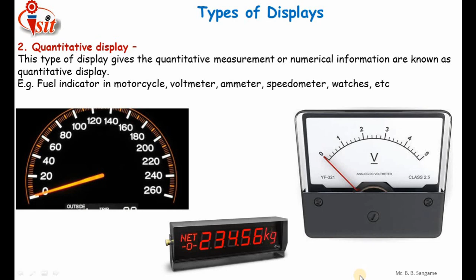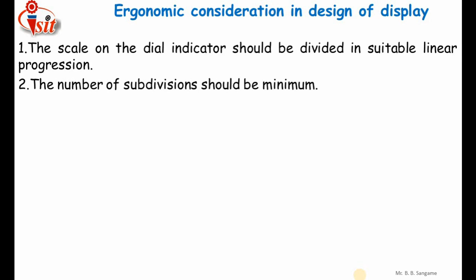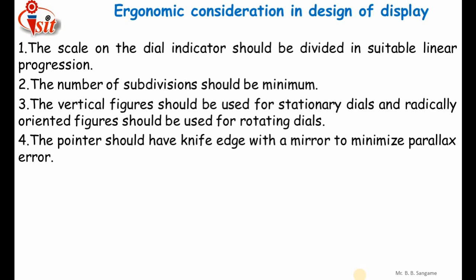Now, the requirements for the scale. The scale on the dial indicator should be divided in a suitable linear progression. The number of subdivisions should be minimum. Vertical figures should be used for stationary dials and radially oriented figures should be used for rotating dials. The pointer should have a knife edge with a mirror to minimize parallax error. Some errors occur while reading displays, so to avoid them, a mirror should be placed behind the pointer.